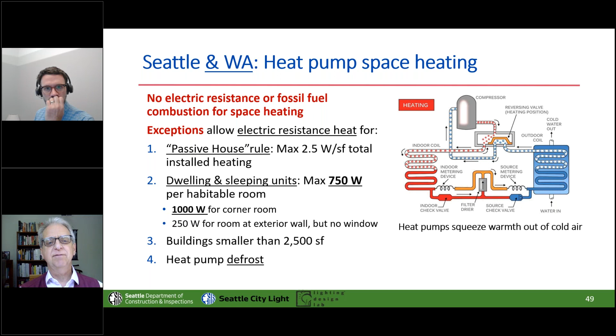You know, there's what I was calling the passive house rule, that if you had a very limited amount of overall heating capacity per square foot of building, that could be electric resistance, you're allowed that 750 watts per room of electric resistance for an apartment or a hotel room, and 1,000 for a corner room. We added one little thing there, that second bullet under item 2, that if you have a room that's at an exterior wall, but it doesn't have a window, that can have a really little heater in it.